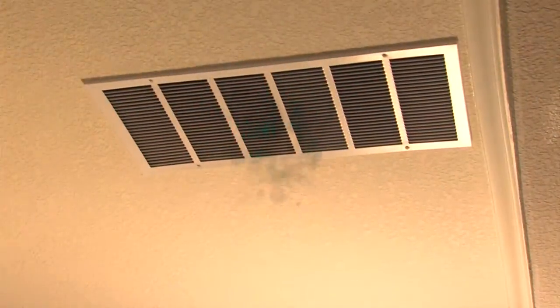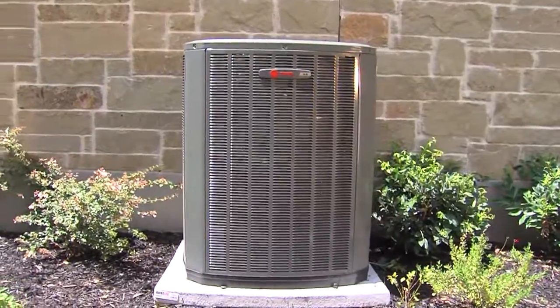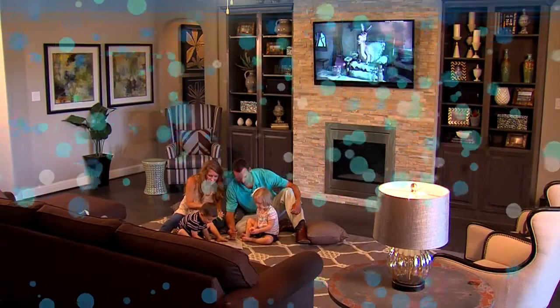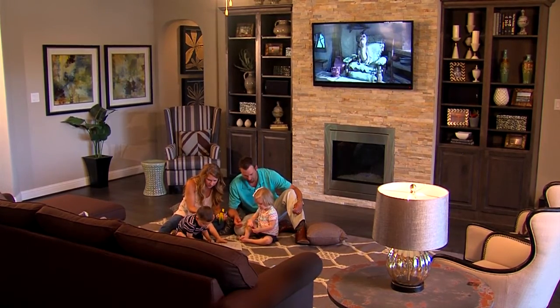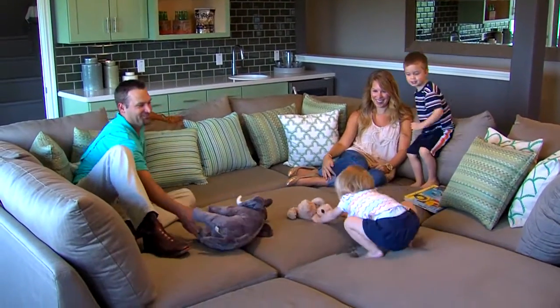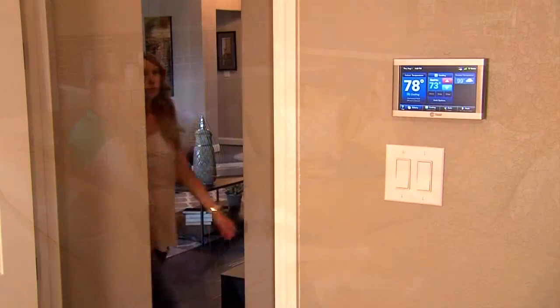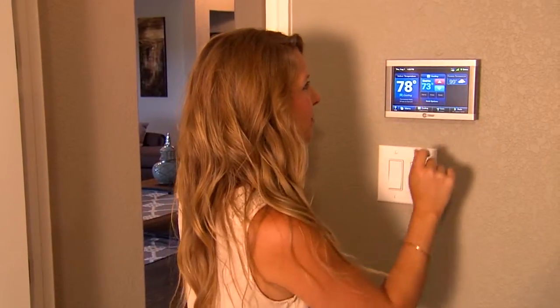It's not temperature, it's humidity. We have humidity in Central Texas, and air conditioners cool the air and make your home comfortable by removing it. To do this, they need to run — not at the expense of higher energy costs, but actually while lowering your utility bill. The fact is, when we lower the humidity in our homes, the house feels cool and crisp rather than damp and cave-like. So as a result, we are comfortable at a higher thermostat setting. Running the system at the lower speed and raising the temperature means your house will be more comfortable and may save energy as well.